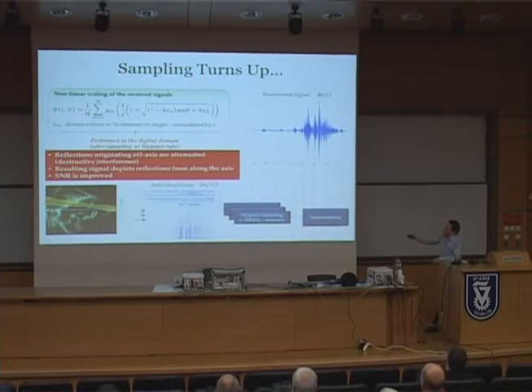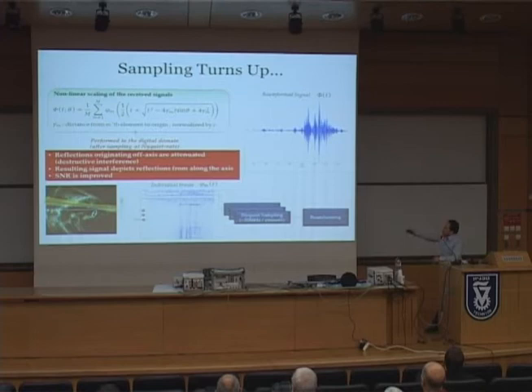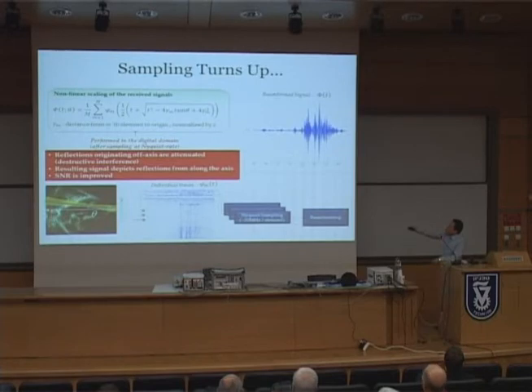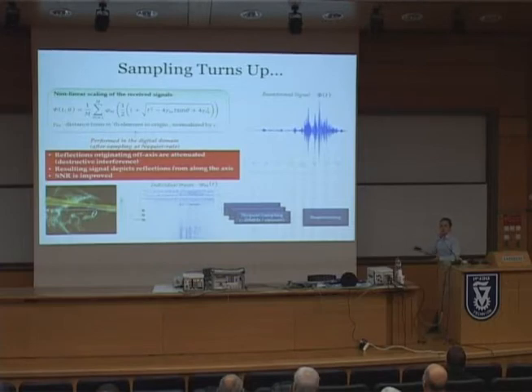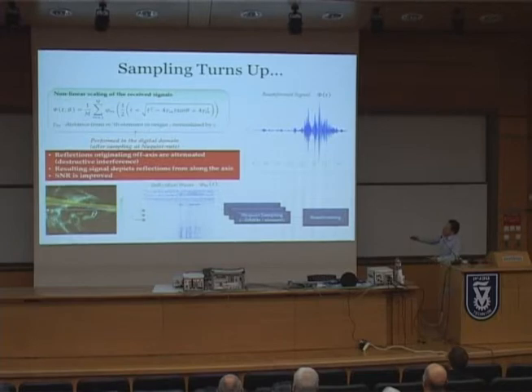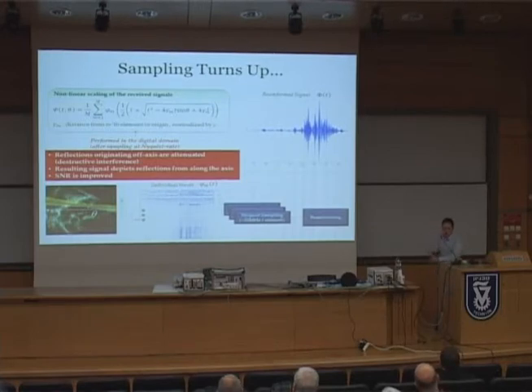The signals phi_m detected by each element have time-varying delays applied to them, which align the signals, and then they are averaged — or summed with some weight in a process known as apodization. Although t is a continuous variable, this is done after sampling the signals at high rates. Since such systems are confined to classic Nyquist sampling theory, these are rates of about 20 MHz, which is twice the baseband bandwidth of the signals. The whole calculation is then done digitally, ultimately enhancing the SNR and attenuating off-axis reflections.